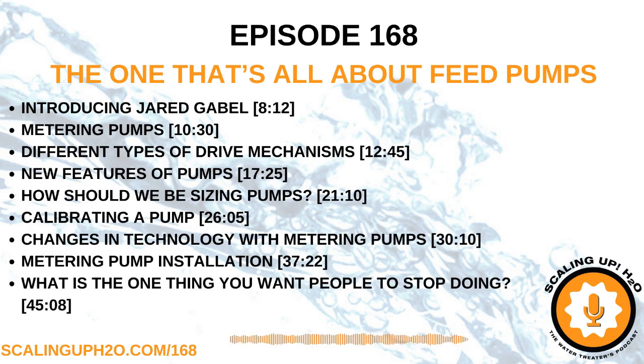One of the number one reasons where we see issues, and basically where we have a lot of success in helping our customers overcome that, is that there are some ways to set the feed rate on the pump, and one of them is the frequency of strokes. On a diaphragm pump, there's a piston in there that moves back and forth to give it that reciprocating motion, and it will either speed up or slow down or happen at different frequencies. Most of the conventional type pumps will have a suction and discharge phase that happens, and then it waits a while. Every time it goes through a suction and discharge phase, it's basically pulling in and pushing out chemistry. And every time you have a waiting period, if you have to inject a lower feed rate, that's one way to set that.